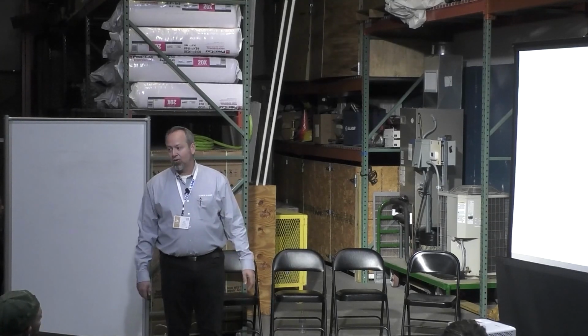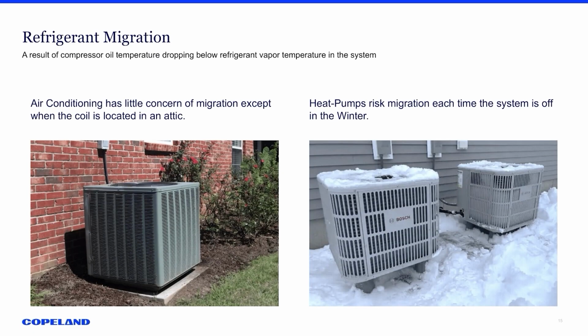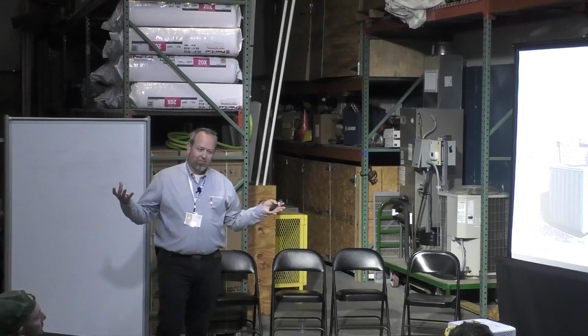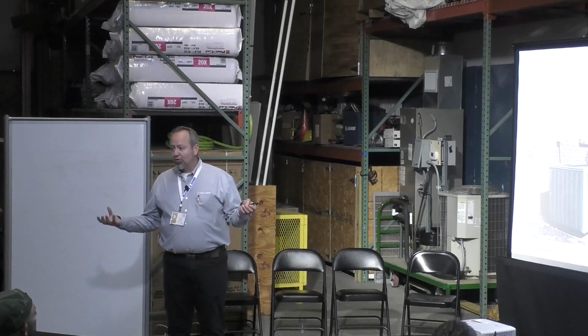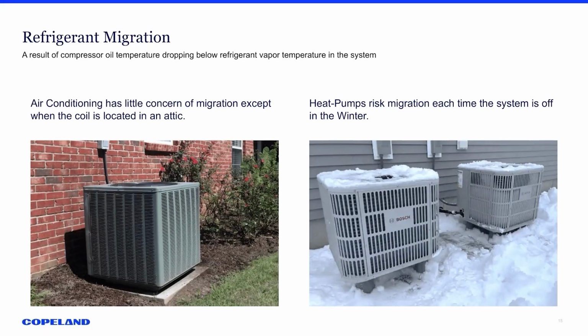And if you're running dual fuel and you're going to get additional heat in by that indoor coil, we'll go through that a little bit here of why that's valuable. Air conditioning has little concern for crankcase heaters, with the exception if you're in an attic somewhere and that attic's super hot, and we're dealing with refrigerant migration. What is that? Well, if you have one area inside or outside that's warmer, when refrigerant gets warmer, it vaporizes, it boils off, and it moves.